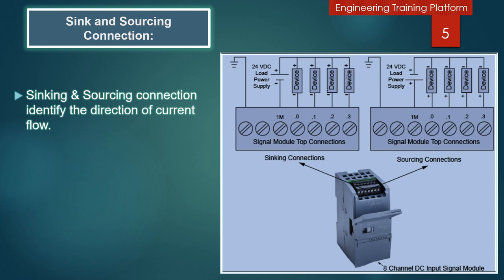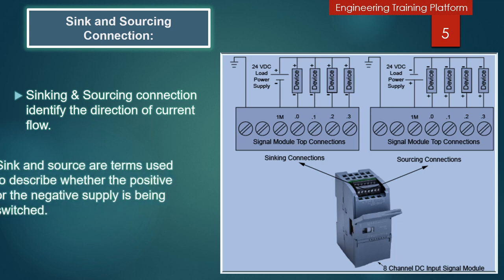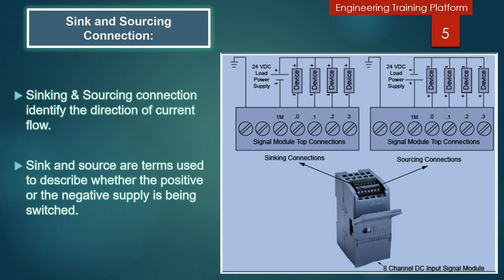Sinking and sourcing connections identify the direction of current flow. Sinking and sourcing are terms used to describe whether the positive or the negative supply is being switched. For the sinking connection, you can see the 24 volt DC load power supply — the positive and negative connections go to the device, and the other side of the device connects to the module. From the load power supply, the negative is directly connected to the module. This type of supply is called the sinking connection.